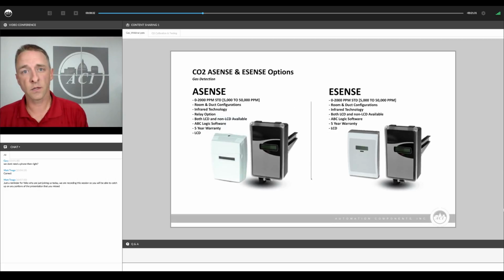Going forward in our CO2 line, we have the A-Sense and the E-Sense lines, and these are also backed by a full 5-year warranty and include the ABC Logic self-calibrating software. These units give you the option of adding an LCD to the enclosures, both for room and duct. The A-Sense gives you the option of adding a relay to the circuit board, and you also have an analog temperature sensor built in with the A-Sense unit as well.